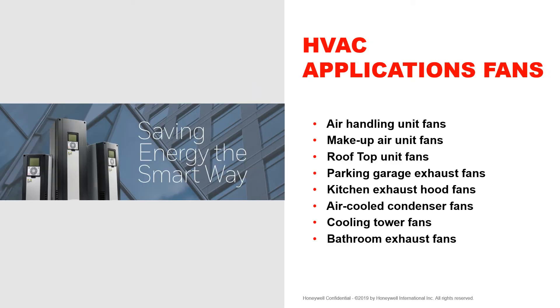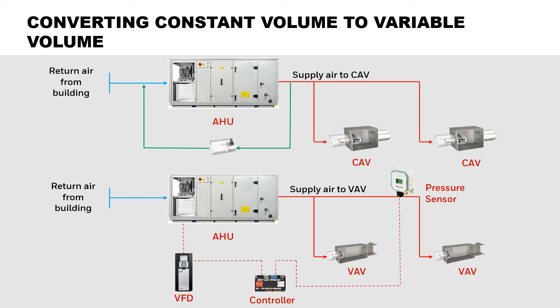These are all the fan applications where VFDs are commonly used to provide energy savings. VFDs are used for a variety of applications. We will go through the most common fan applications that use VFDs. The image on top depicts a typical constant volume air-based HVAC system. Although an air-based system is shown, the same concepts apply to water-based systems. In a constant volume system, the supply fan or system pump will typically run at a constant speed of 60 Hz. This system typically employs either a bypass damper or a three-way bypass valve to regulate the pressure produced by the main supply fan or system pump.